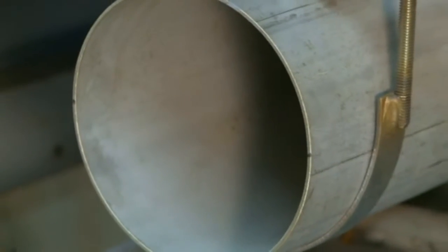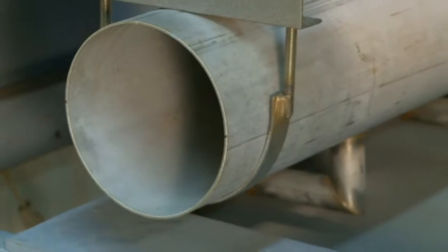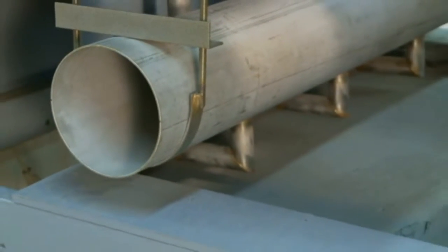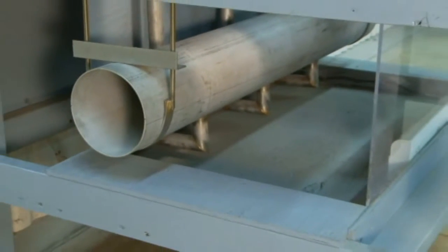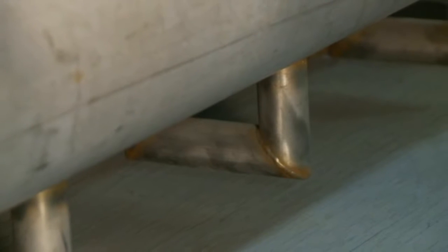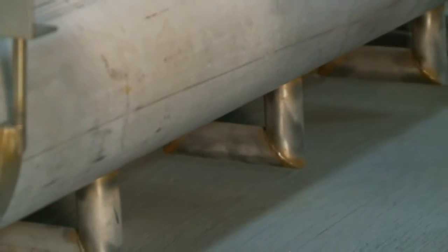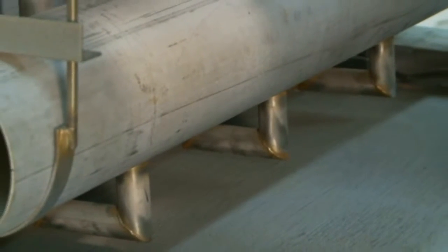The area here is the front flume where filtered water is collected, backwash water is distributed, and the air header pipe is located. In existing installations, if there is enough area in the front flume to not increase backwash water velocities, the air header with J risers is placed.